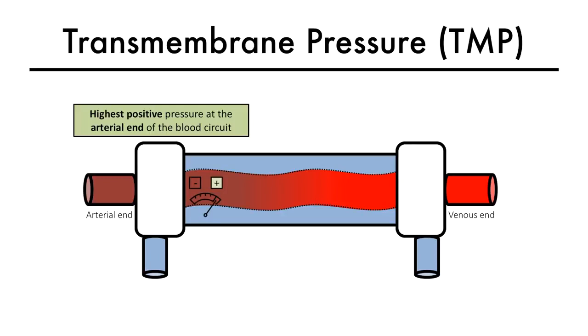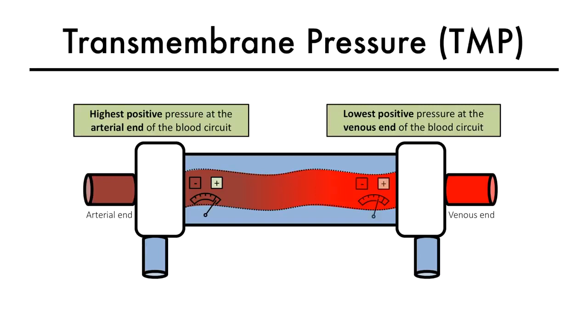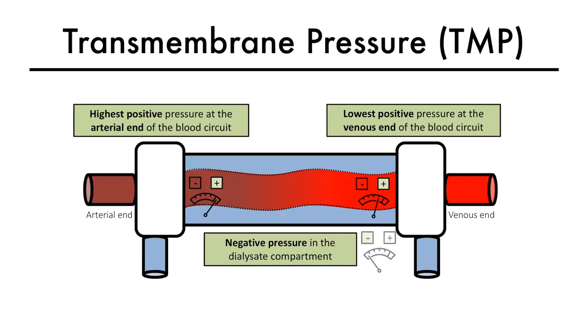Here is a cartoon of the hemodialysis filter. The highest positive pressure is seen at the arterial end of the blood compartment. The lowest positive pressure is seen at the venous end of the blood compartment. A negative pressure is seen in the dialysate compartment. This pressure gradient allows for movement of water across the membrane from the blood to the dialysate.